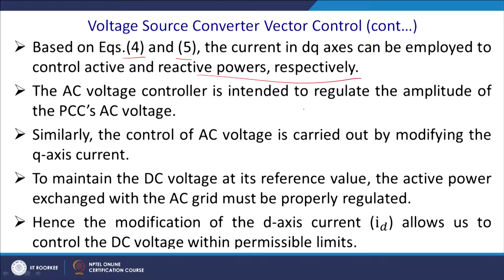The voltage controller is intended to regulate the amplitude of the voltage at the PCC. When you have a voltage disturbance — sag or swell — that enters the control chain. Sag and swell can be controlled by modifying the Q-axis current. For example, if you terminate a load with a capacitor, the terminal voltage will swell up; you then require a change in Q-axis current. In normal healthy conditions, this Q-axis current adjustment is not touched.